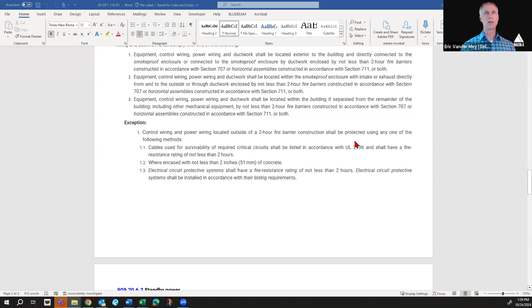As we discussed last week, going up to the latest language, in red here we discussed removing the reference to the 2020 NEC and instead referring to NFPA 70. All other sections of the code that refer to NFPA 70 refer to it that way, and then you go to the reference standards section of the code to find the applicable version, which would be the 2023 version. The 2023 NEC is adopted for both the 2021 Washington State Code as of now and is the reference standard in the 2024 IBC.